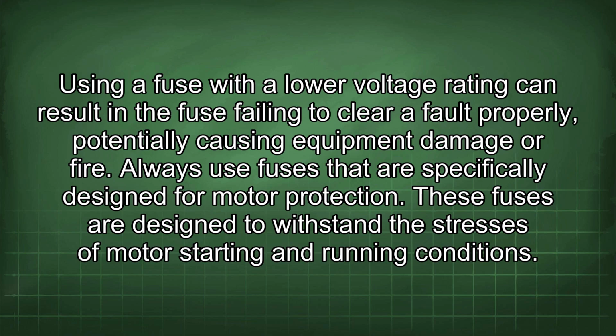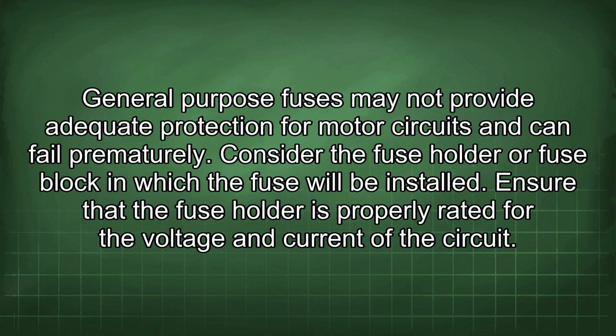Always use fuses that are specifically designed for motor protection. These fuses are designed to withstand the stresses of motor starting and running conditions. General-purpose fuses may not provide adequate protection for motor circuits and can fail prematurely. Consider the fuse holder or fuse block in which the fuse will be installed.